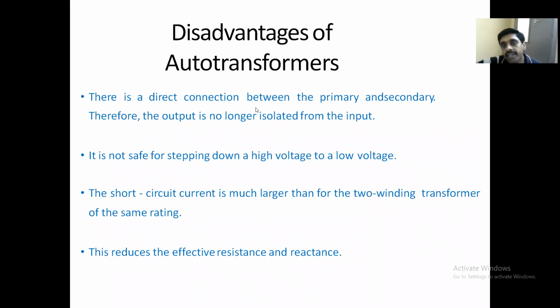There is a direct connection between primary and secondary. Therefore, output is no longer isolated from the input. Directly they are connected, primary, secondary, they are connected. So we can say that output is no longer isolated from the input. Normally, transformer means there is an isolation from input to output. It is not safe for stepping down a high voltage to a low voltage.